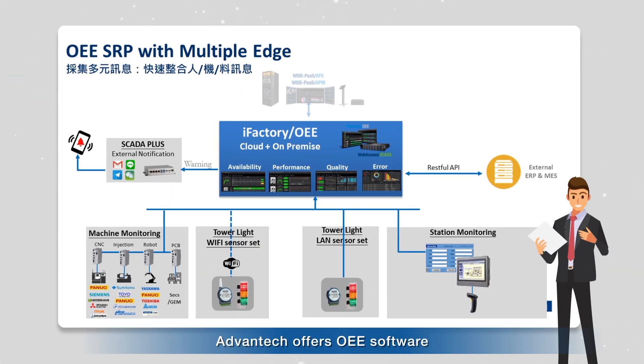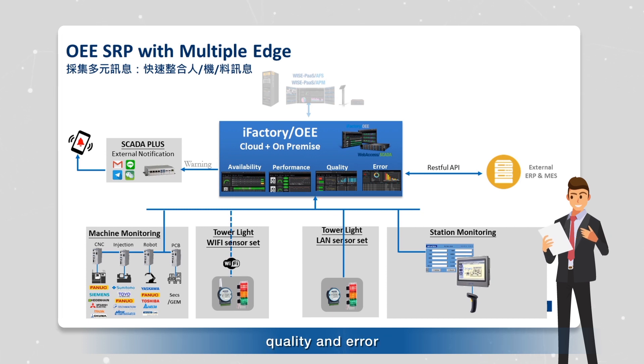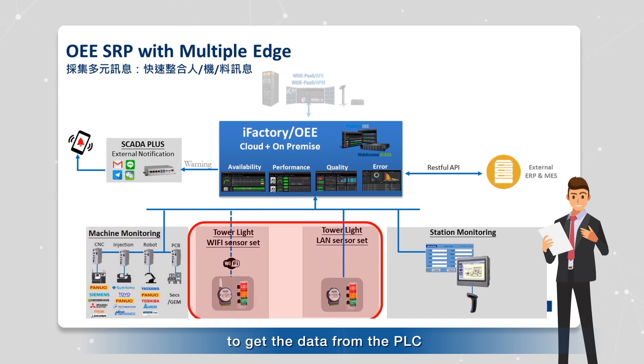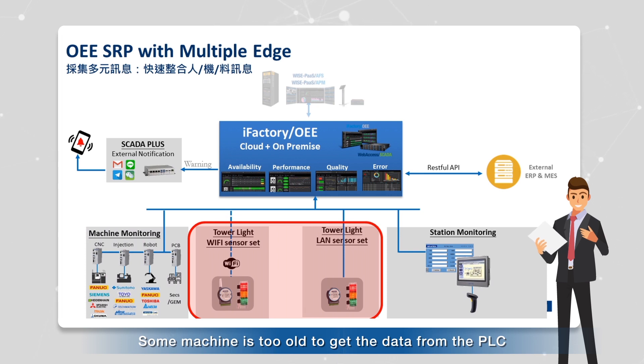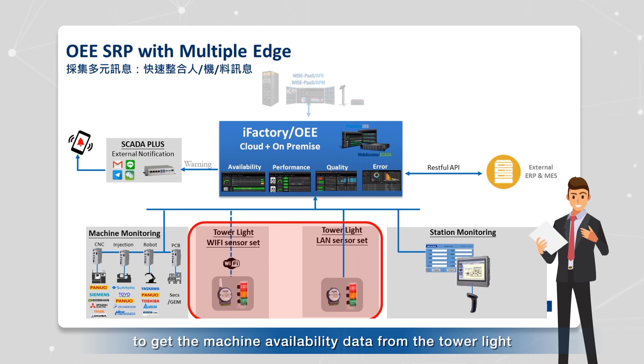Advantech offers OEE software and also offers an entire data acquisition edge to collect data for OEE availability, performance, quality, and error reporting. For availability, Advantech provides a WebAccess PLC driver to get data from the PLC. For older machines where it's not possible to gather data from the PLC, Advantech provides a detachable tower light sensor to gather machine availability data from the tower light.